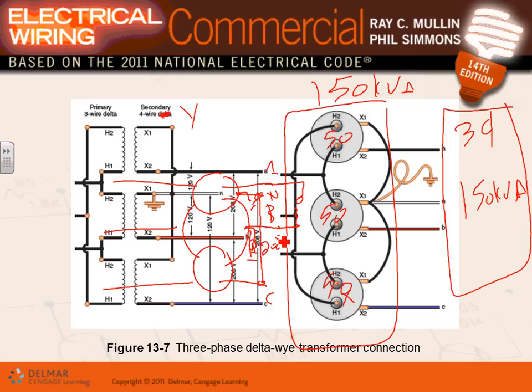So on a center tap delta, what is the voltage on it? It's like a three-phase center tap delta. What happens? The only reason why we center tap a delta is to get line-to-neutral 120 from a three-phase system. The only reason. So 208/120, don't think about it. 480/277, don't think about it. The only reason why we have a center-tapped open delta or closed delta is to get 240/120 three-phase. The only reason.